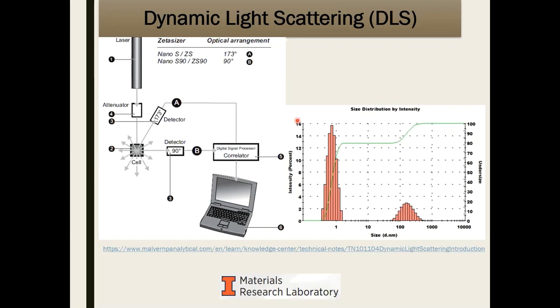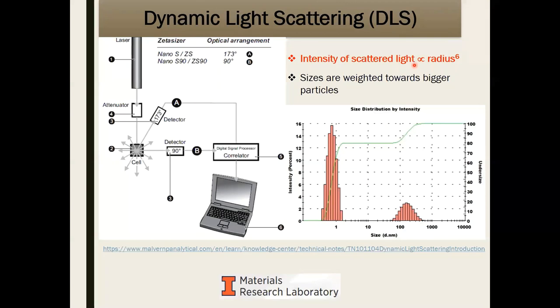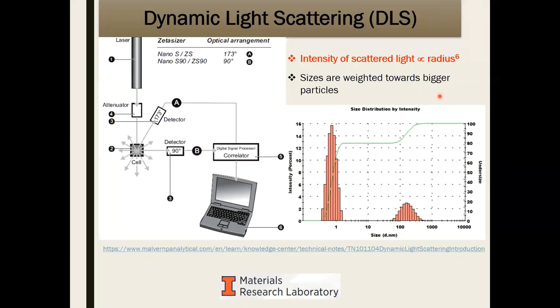If you remember nothing else about light scattering: the intensity of scattered light is proportional to the radius of the particle to the sixth power. If you have two particles and one is twice as big as the other, the larger particle will scatter 64 times more light than the smaller one. This means the technique is heavily weighted toward larger particles — even just one large particle can significantly affect your data and analysis. Remember: light scattering intensity is directly proportional to the radius to the sixth power.